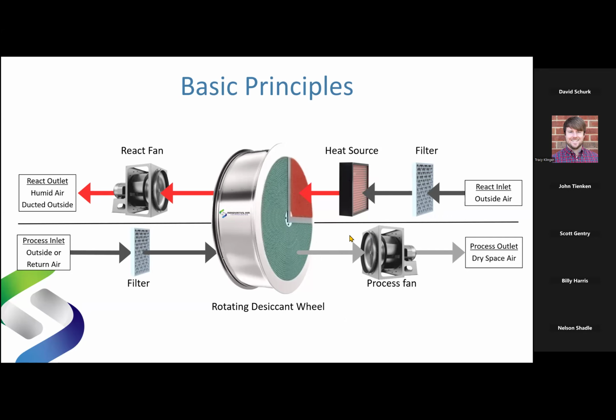Now, this air has also been warmed up. So it leaves the wheel warm and it leaves the wheel dry, perhaps incredibly dry. The air here may leave up to 100 degrees Fahrenheit. It just depends, right? That is the latent heat of adsorption. It's very similar to the latent heat of condensation that I mentioned occurs in traditional cold coil systems. It's just I haven't taken it out of the air yet. I've left it there. Now, if I want to, I can put a post-cooling coil right here, and I can cool that air down from 85, 95, 100 degrees Fahrenheit, whatever it comes off the wheel at, depending, down to 55, 45, 35, 25, minus 25, minus 40. Doesn't matter. This air's dry. The coil that is in the process post-cooling coil position will run dry. It's sensible only. So I can have air as cold and dry as I want it to be. The sky's the limit. Boy, you can't do that with a traditional system, can you? That's pretty cool. That solves a lot of problems.